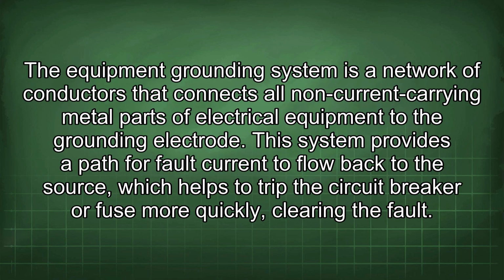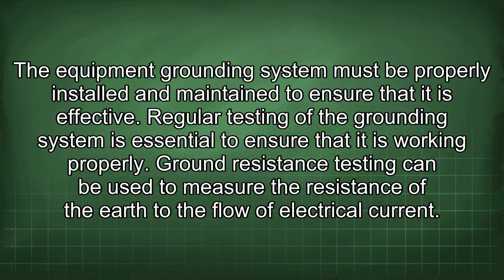The equipment grounding system is a network of conductors that connects all non-current carrying metal parts of electrical equipment to the grounding electrode. This system provides a path for fault current to flow back to the source, which helps to trip the circuit breaker or fuse more quickly, clearing the fault. The equipment grounding system must be properly installed and maintained to ensure that it is effective. Regular testing of the grounding system is essential to ensure that it is working properly.